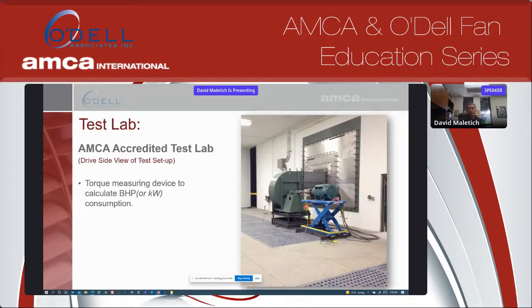On the drive side of the fan, the fan's being driven by a motor through a VFD. A lot of times people think, hey, I'm just going to get the amp readings and everything off the motor VFD package. The problem with that is that those items are not calibrated. Typically, it's very difficult to calibrate a motor VFD at all the different load ratings that the motor VFD package might see. So consequently, most fan manufacturers are going to use some load cell device, such as a torque meter, to record energy consumption of the fan.